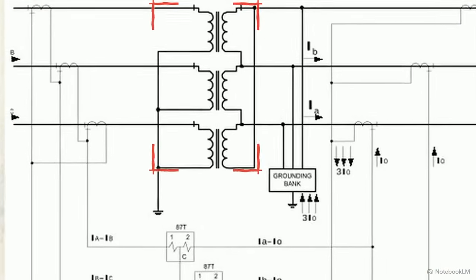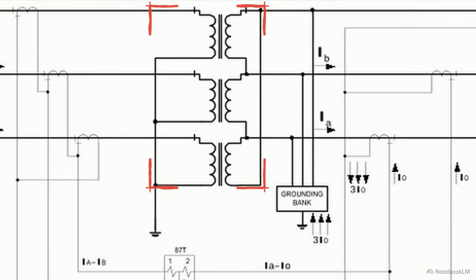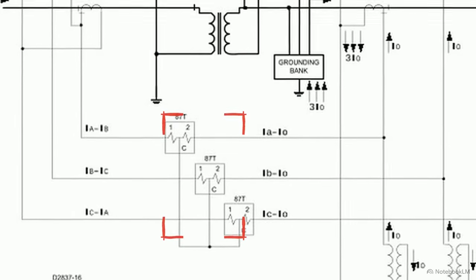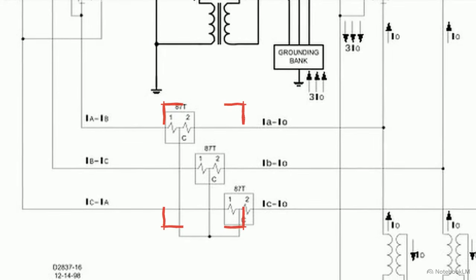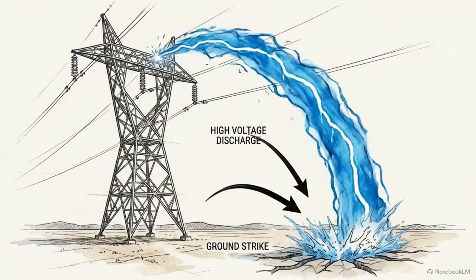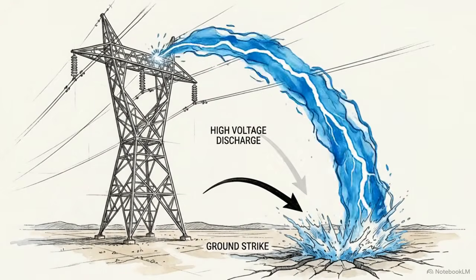This schematic of a substation shows transformer windings, a grounding bank, and a protective relay architecture, all designed to manage massive fault energies. When immense power lines fault, a staggering amount of current is dumped directly into the earth. But dirt naturally resists electrical flow, preventing it from absorbing all that energy instantly. This creates ground potential rise.